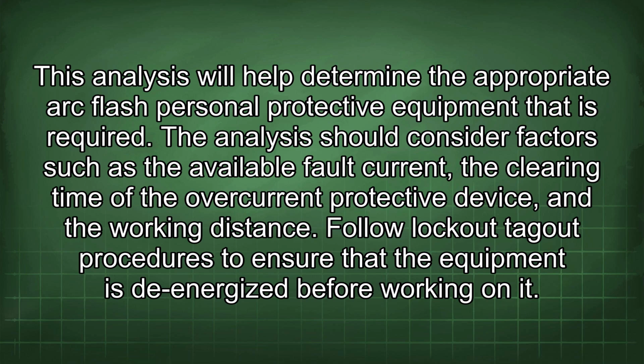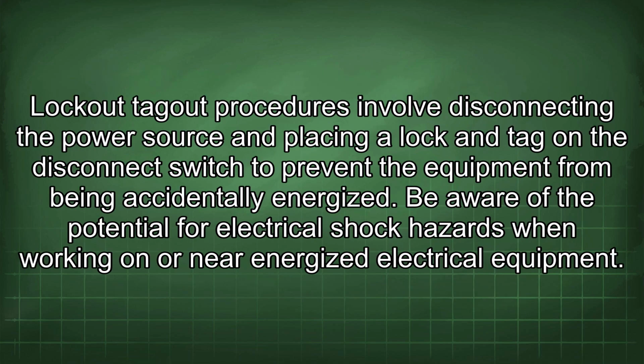The analysis should consider factors such as the available fault current, the clearing time of the overcurrent protective device, and the working distance. Follow lockout-tagout procedures to ensure that the equipment is de-energized before working on it. Lockout-tagout procedures involve disconnecting the power source and placing a lock and tag on the disconnect switch to prevent the equipment from being accidentally energized.